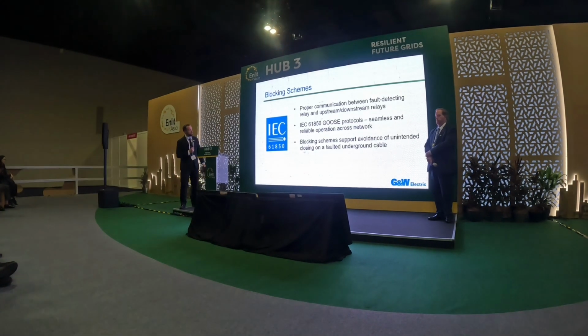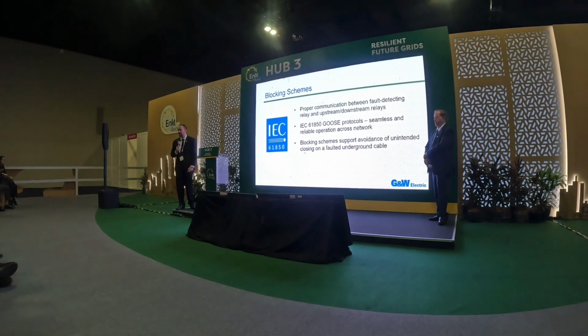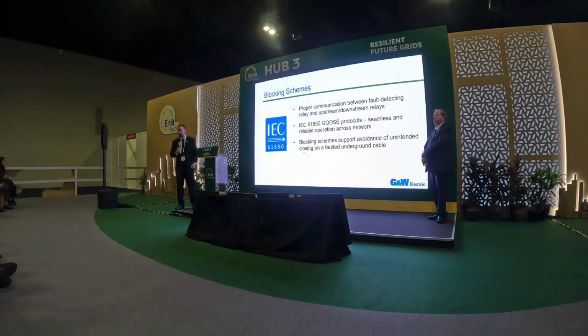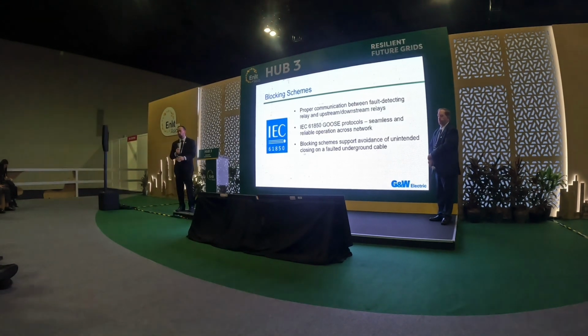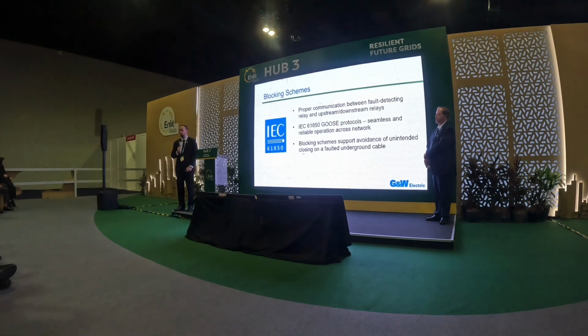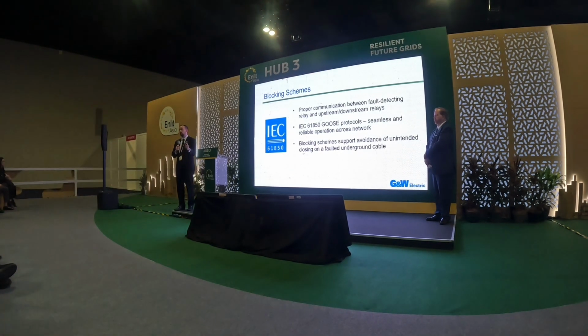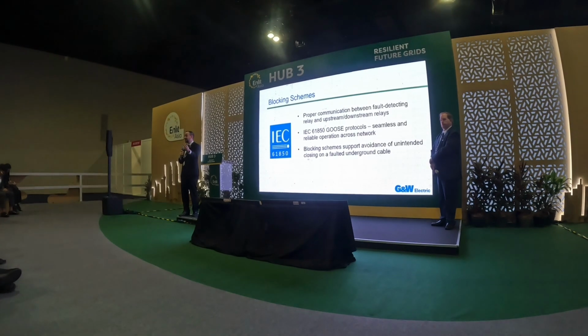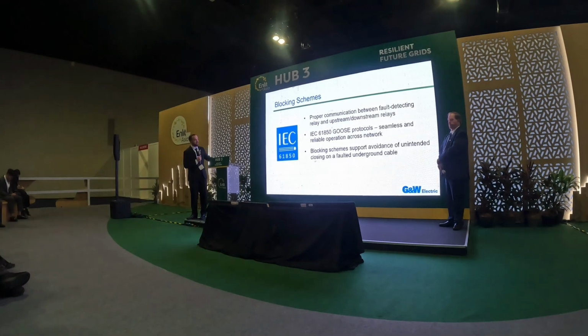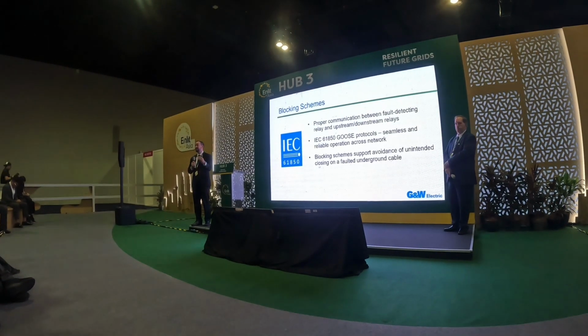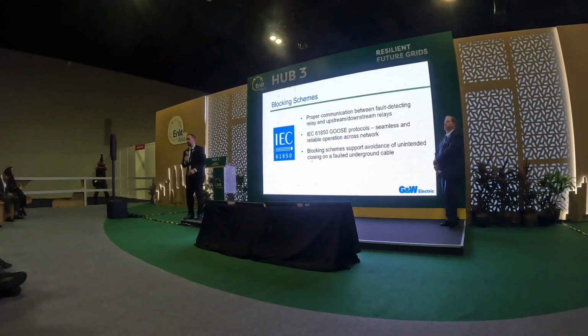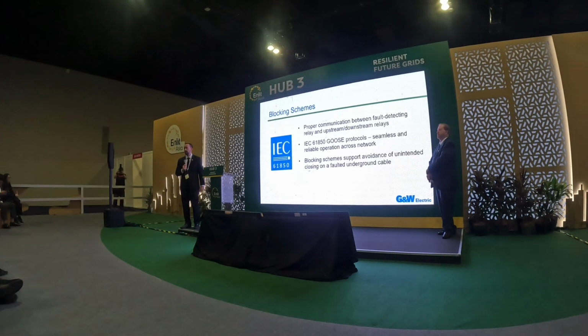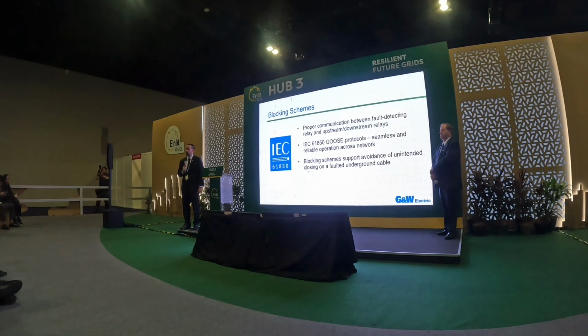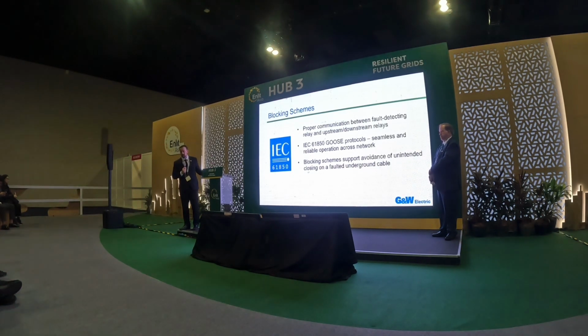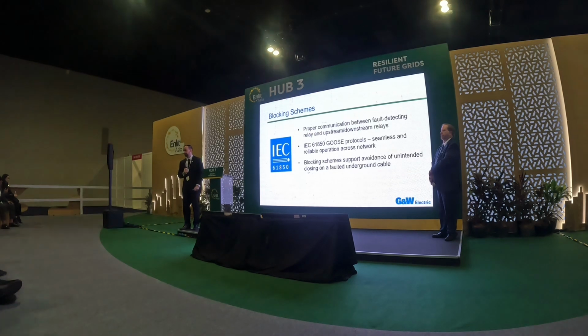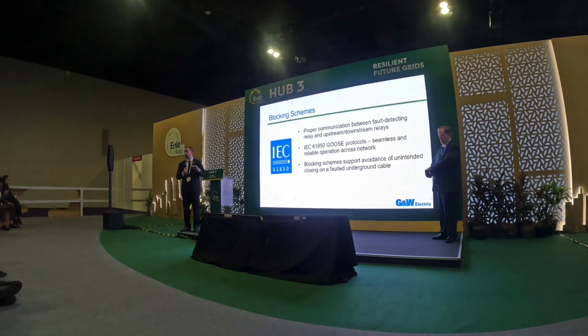So again, by taking advantage of open standards in the industry, IEC 61850 is a standard that has a number of different protocols and functionality, but within it there is a messaging protocol called GOOSE that allows for very high-speed communication between different IEDs, relays throughout your grid. They were able to create a scheme where they detect through that differential protection where the fault is, and then communicate a block signal to that relay on the recloser to ensure that it does not operate again and prevents them from having a very serious failure like they did.